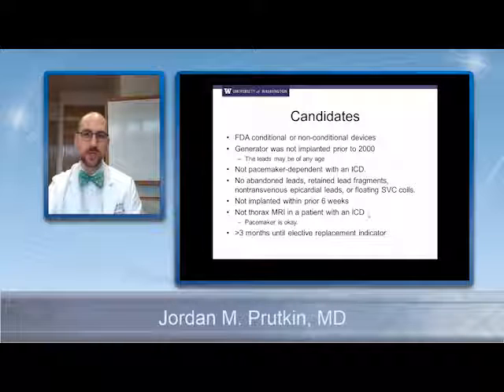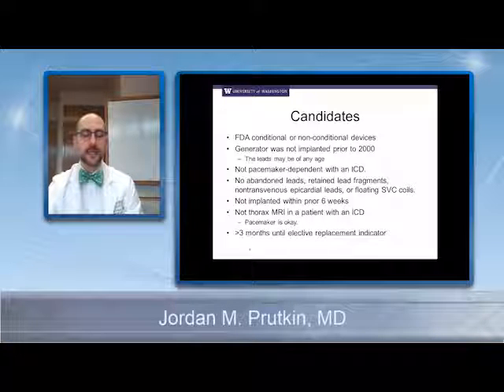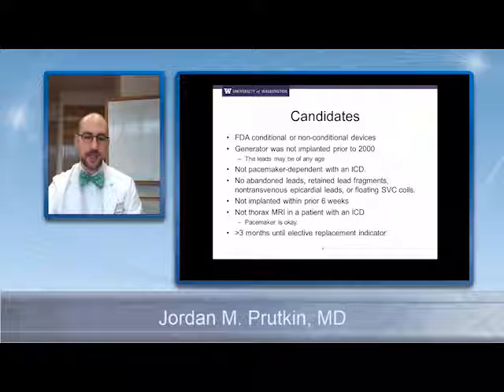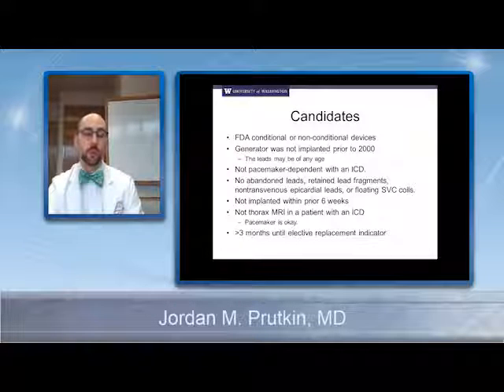And part of that just has to do with imaging quality. You need some specific MRI sequences to be able to still see the heart with an ICD. We don't have this issue with pacemakers, so we will do MRIs of the heart in people who have pacemakers. And then there has to be greater than 3 months until elective replacement indicator, or until the time that you have to replace the battery. So if you have someone whose device is nearing the time that it has to be replaced, what we don't want to happen is that the MRI scan drains that last little bit of juice still in the battery, and then we make them reach elective replacement. So typically we'll say that they should either have their device changed out first, or that the MRI scan is delayed for that greater than 3 month window.